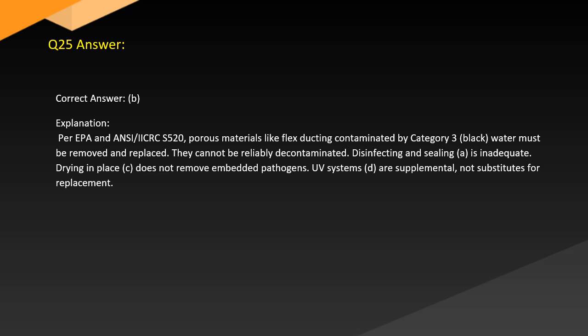Answer. Correct answer: B. Explanation. Per EPA and ANSI/IICRC S520, porous materials like flex ducting contaminated by Category 3 black water must be removed and replaced. They cannot be reliably decontaminated. Disinfecting and sealing (A) is inadequate. Drying in place (C) does not remove embedded pathogens. UV systems (D) are supplemental, not substitutes for replacement.